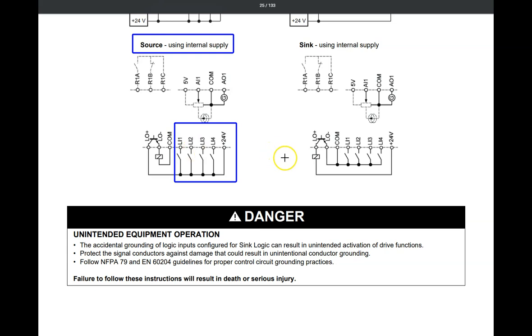As this drive does not have a dip switch, it has a parameter. If you prefer to use sink wiring, you take a wire from your common right here. You place it on one side of the switch. When you close the switch, you have your zero volt common level at those switches. And the drive will respond. That will be a run command. And again, you have to set the parameter accordingly.